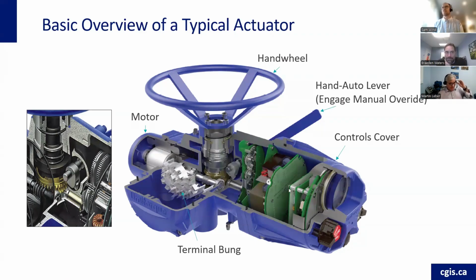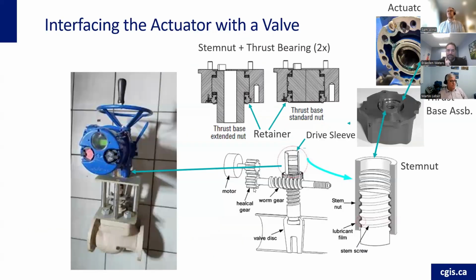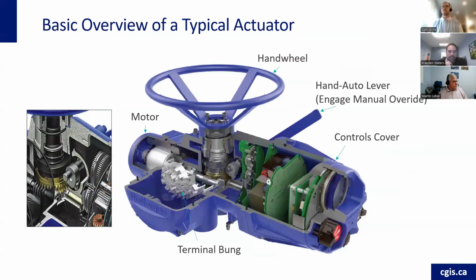So that's just a very basic overview of an electric actuator. Now, how does the electric actuator connect to interface with the valve? I'm going to go back to this drawing and focus in on this. There's a worm shaft and a worm wheel, an aluminum bronze worm wheel. That interconnection is where the motor shaft transfers the torque to the worm wheel. That's critical—that's really where it all begins.